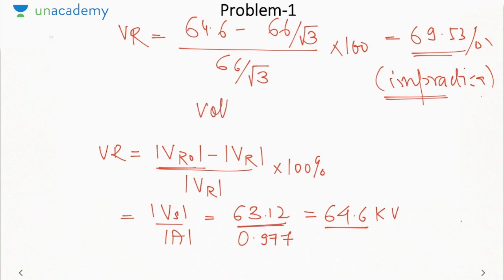These sort of systems are called voltage unstable, because there is a large decrease in voltage from no load to full load. We will say that the voltage collapses as we increase the load on the system, hence it is voltage unstable. Okay, so these sort of systems are undesirable. That is why steady state analysis is important to judge these type of condition. If such condition exists, then that transmission line is useless for us.